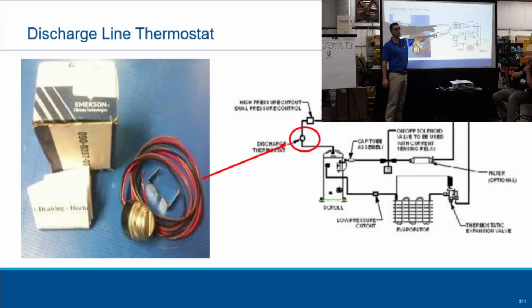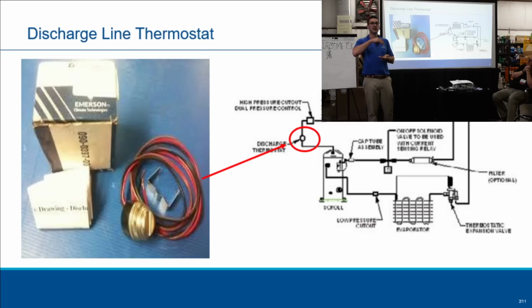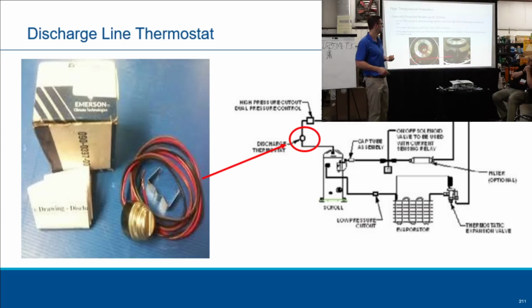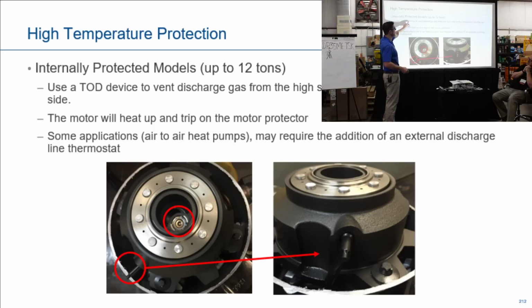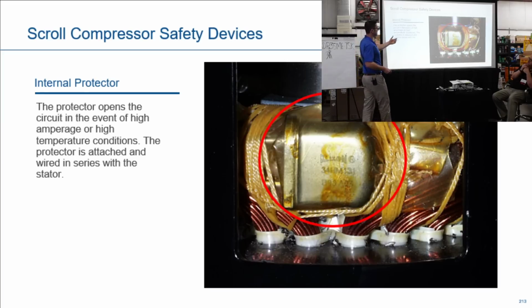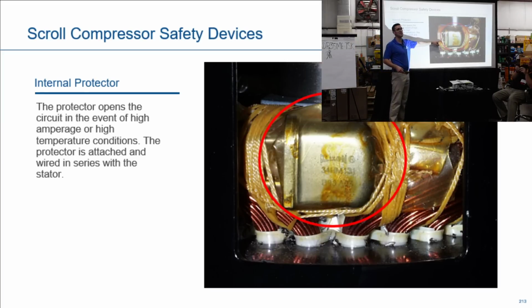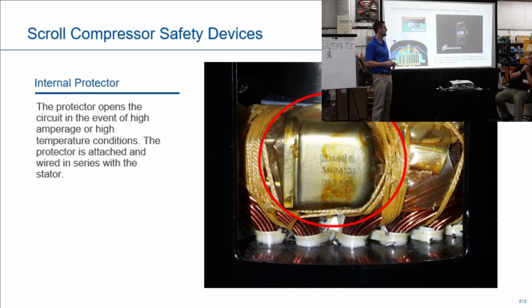Overheat protection devices, we have lots of different ones, but this one here you can just put on your discharge line and wire it up. If you reach that temperature over 225 or 250, it'll cut the compressor out and protect it. We have different devices like this, the TOD that we talked about: if that temperature or amps go up higher, this bimetal disc opens up and shoots discharge gas onto that motor protector, stopping the compressor from running. Well, this is the protector here, amps and temperature. This will open up as that temperature rises, you're going to get overheat, shut that compressor down. Like I said, all these different compressors have different internals on them. You've got to be aware which ones are inside that compressor you're working on.